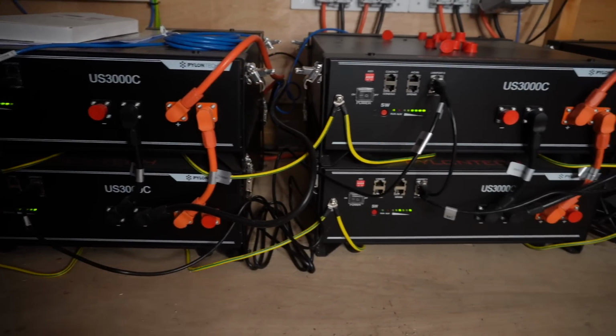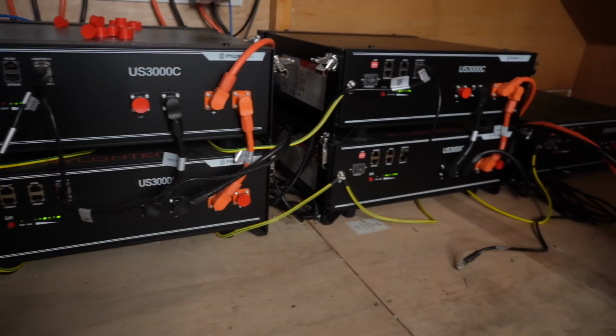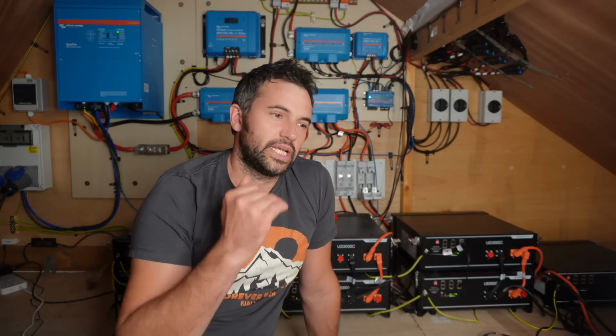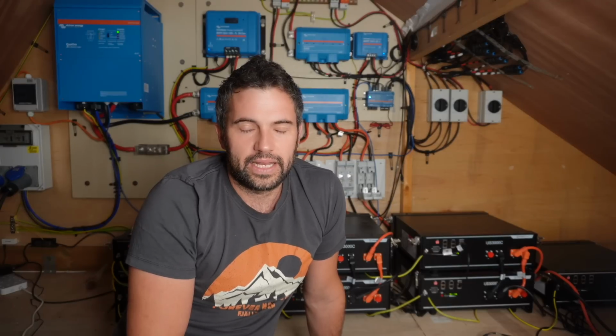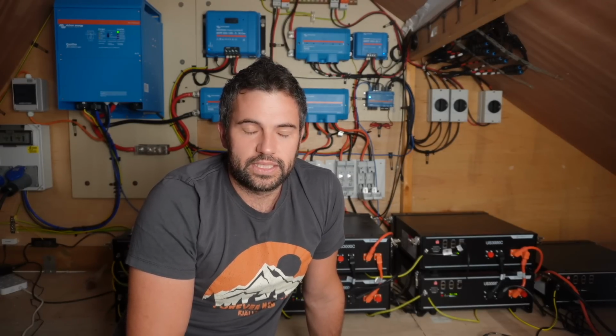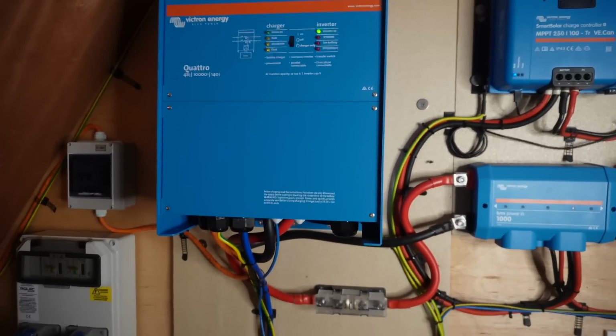Okay, so we've wired our batteries wrong, and we should put them all in one stack and use one long set of DC cables. I've had people say this that have said they're installers. There's a good reason why we used more than one set of cables, and it's not just about batteries and storage. If you've got a big inverter, it draws a lot of power. Say you've got a 3 kilowatt inverter and 8 batteries because you want storage, you're not particularly pushing power, then that would probably be fine. But when you've got a 10 kVA inverter, it's very different.